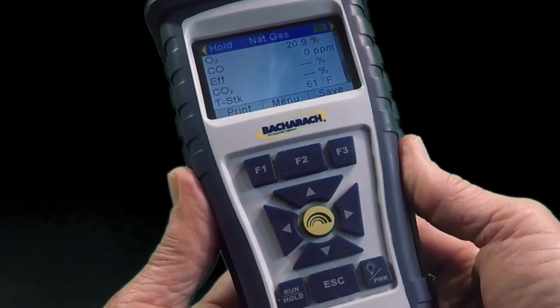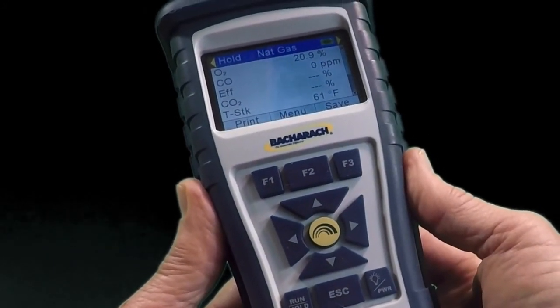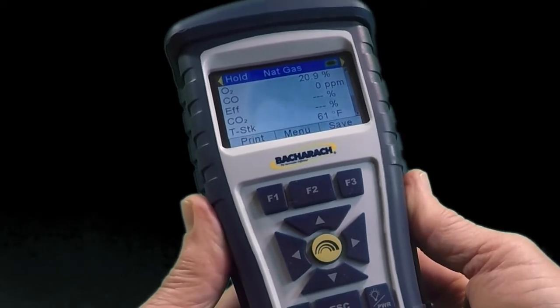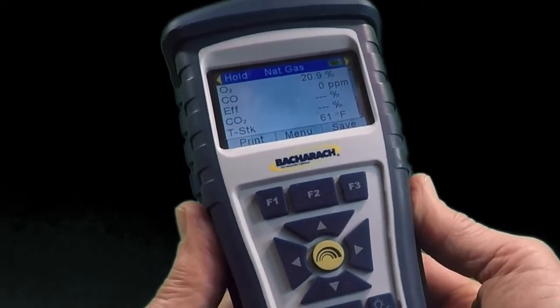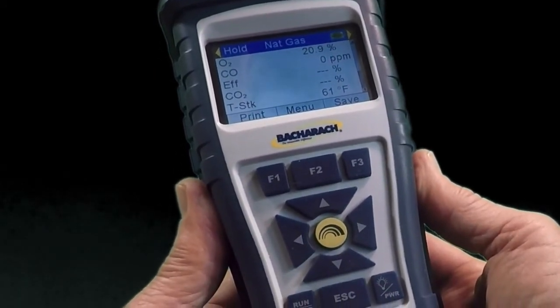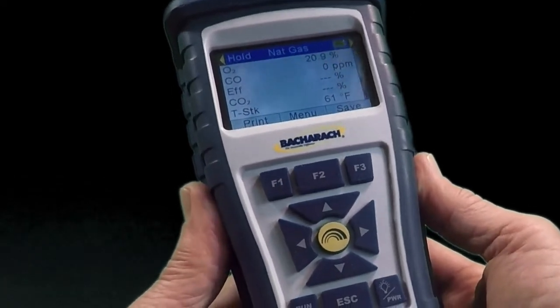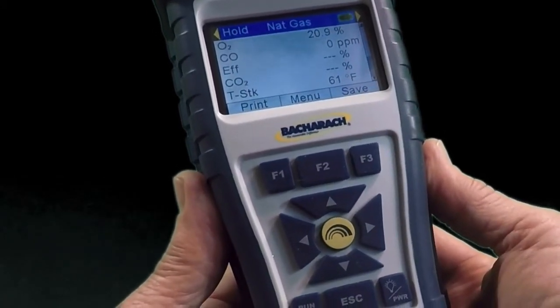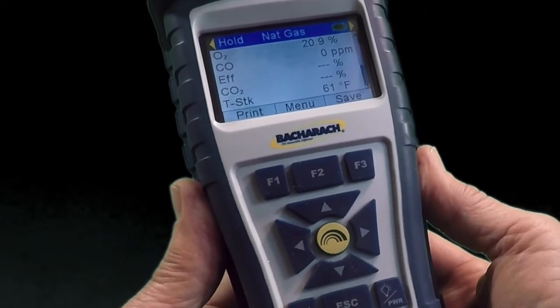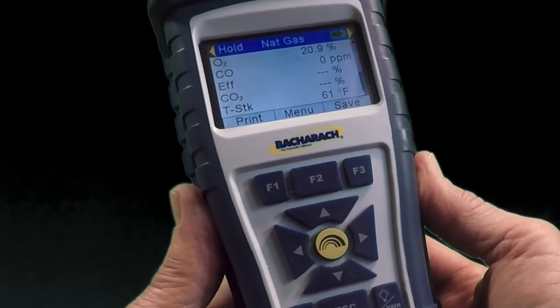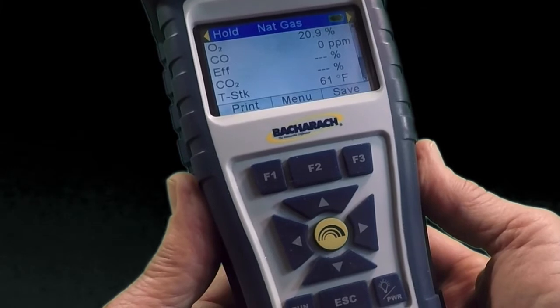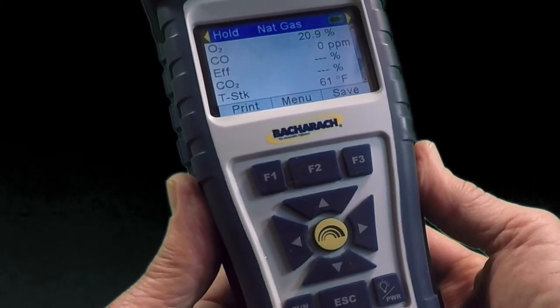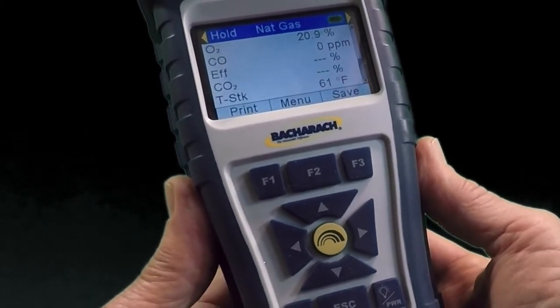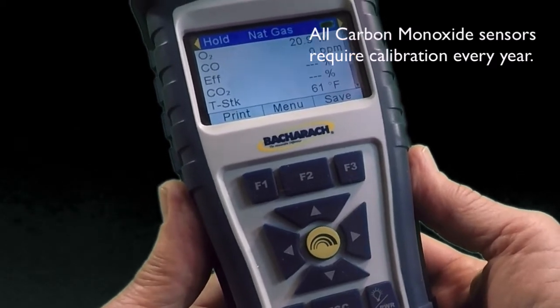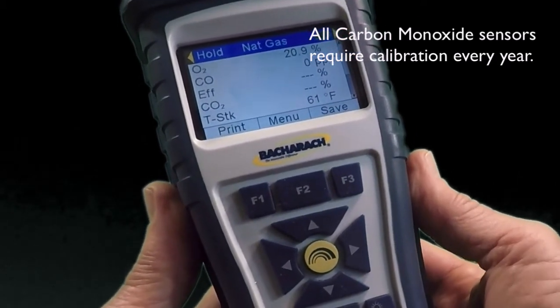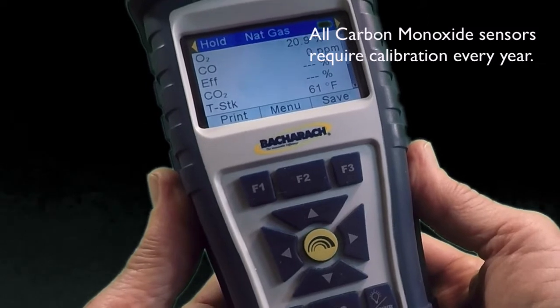If it comes up with repeated sensor error messages in clean air, it could suggest the CO sensor's reached the end of its useful service life, but frankly that's unlikely. Bacharach uses very good quality, long life sensors. The CO sensor is electrochemical in nature. That means the more CO that it's exposed to, the shorter the sensor's life will be. They should last many, many years, although like all manufacturers' carbon monoxide sensors, they do need to be calibrated every year. More on sensor calibration later.